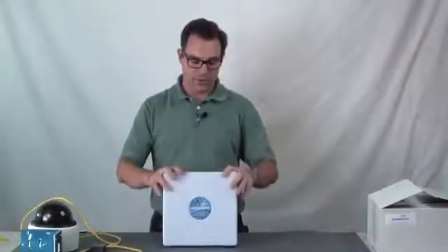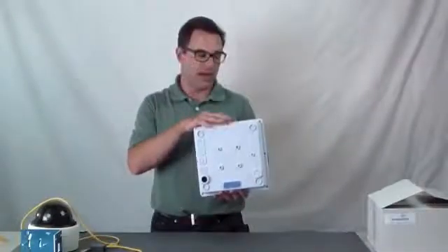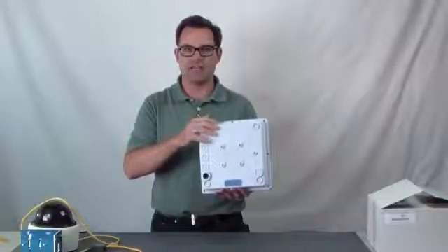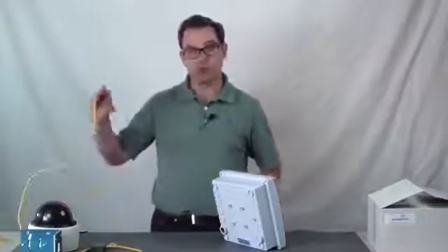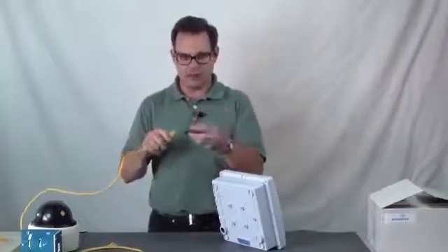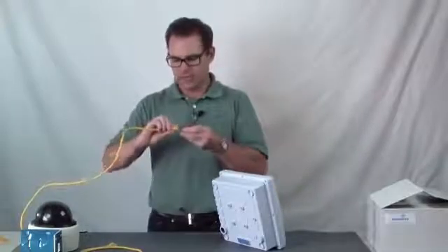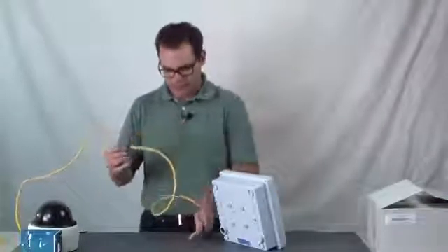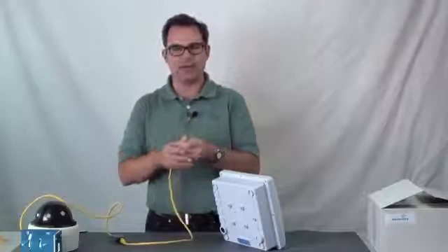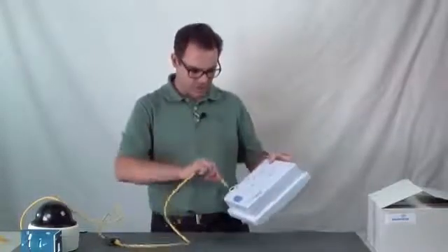Now here we are with the client radio at the camera side. The AP is all set up, waiting for a link. Same basic installation process here. It's the exact same enclosure, just pre-configured as client or AP. As we start to install, we take our patch cord from our camera, we take our power injection module, and connect it to the in port. We take a second patch cord, connect it to the out port. Then we're going through the same process of adding all the gland pieces onto the cabling itself.